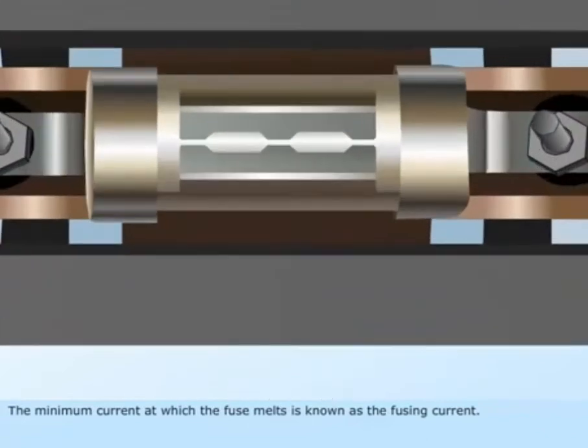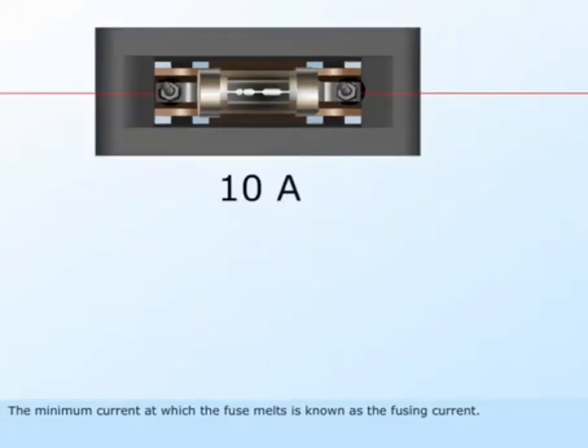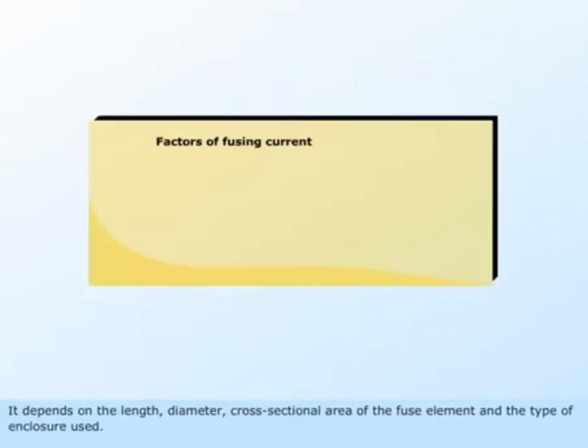The minimum current at which the fuse melts is known as the fusing current. It depends on the length, diameter, cross sectional area of the fuse element and the type of enclosure used.